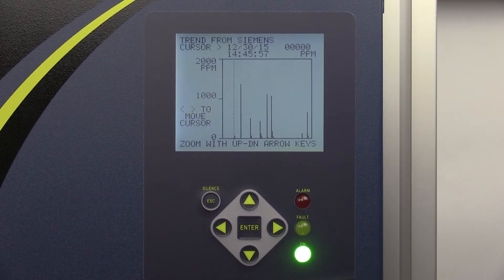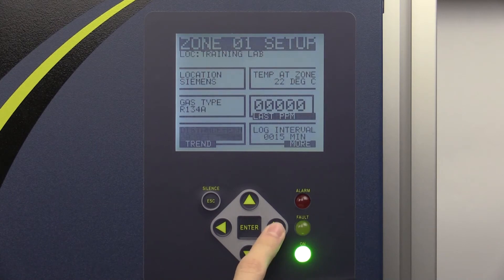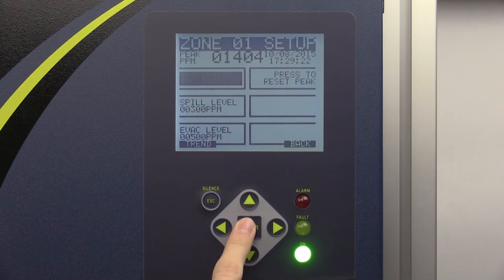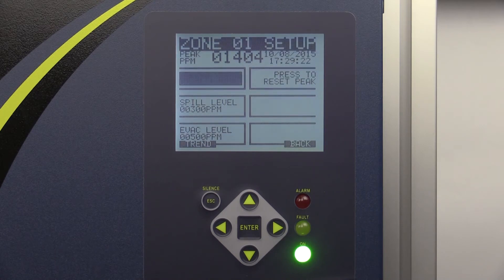Select the More option on the first Zone Setup screen and access the second Zone Setup screen. From this screen, you can set the leak, spill, and evacuation levels for that specific zone. You can set these values to whatever level you would like. However, they must increase sequentially from leak level to spill level to evacuation level.